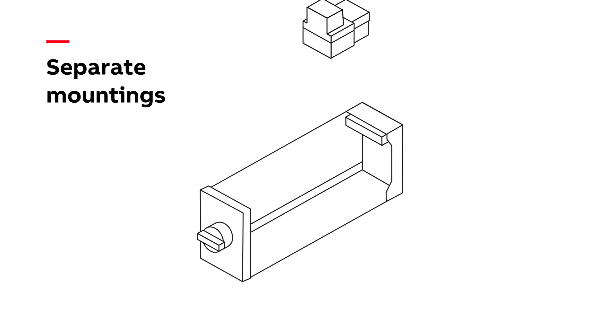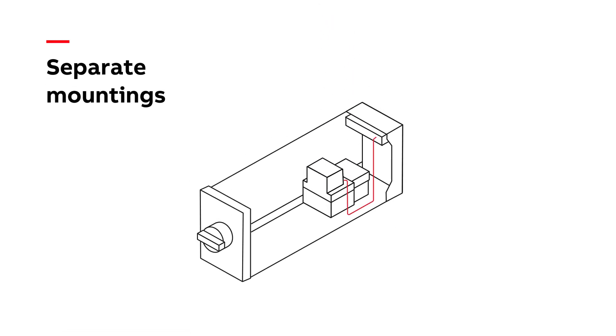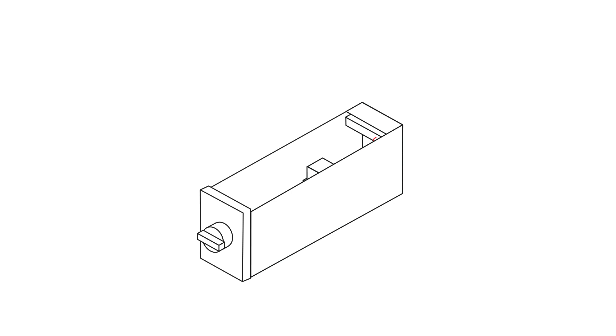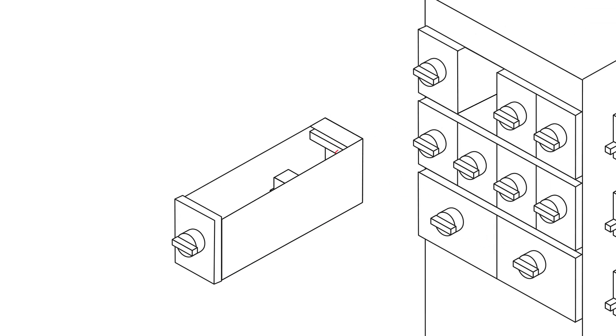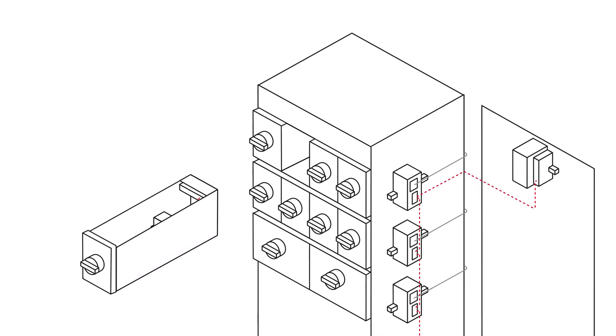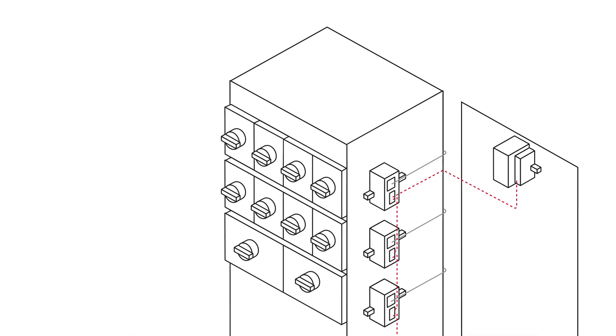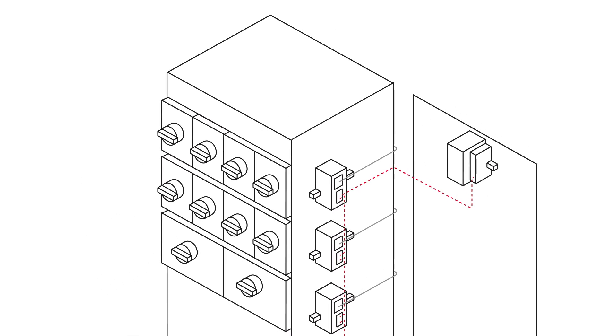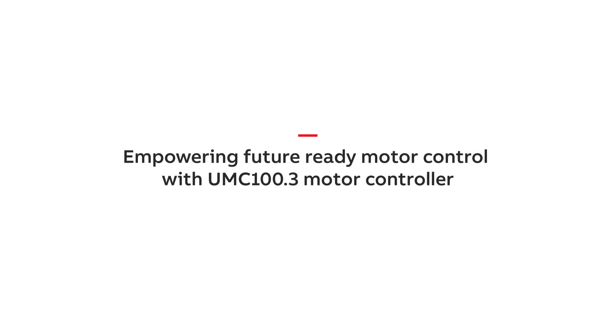The modular design allows separate mounting of communication modules outside the drawer in the cable compartment, benefiting ring topology by avoiding drop lines and enabling fast drawer replacement without communication loss between DCS and communication modules. No configuration of the communication module is needed, and parameterization can be automatically downloaded into the exchanged UMC drawer. Empower your future-ready motor control with the UMC 100.3.